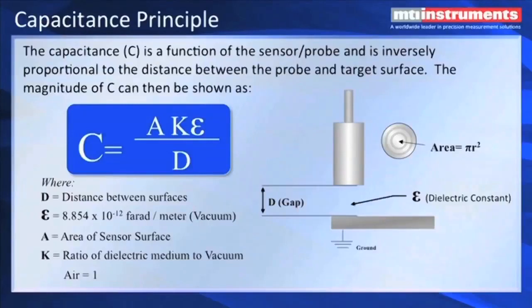A little of the science behind the capacitance measuring principle. Capacitance is equal to the area of the probe times the ratio of the dielectric constant of the medium, which is typically air, to vacuum. In vacuum, it would be 8.854 picofarads per meter. And typically the difference between air and vacuum is 1-to-1 for all practical purposes. We also have the distance, the gap from the face of the probe, and as that gap increases, then the capacitance is obviously going to get smaller. If we increase the area of the probe, you can see that the capacitance is going to go up. So it's a trade-off between the gap you want to measure and the size of the probe.